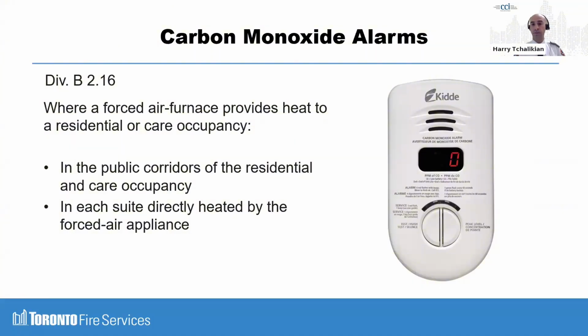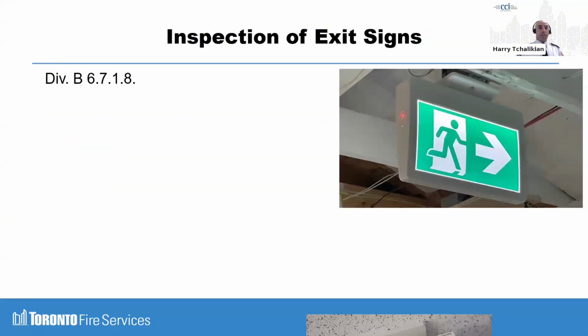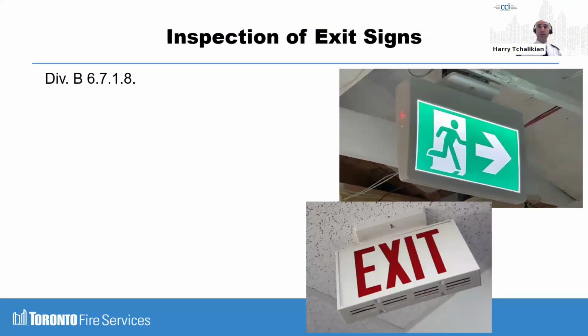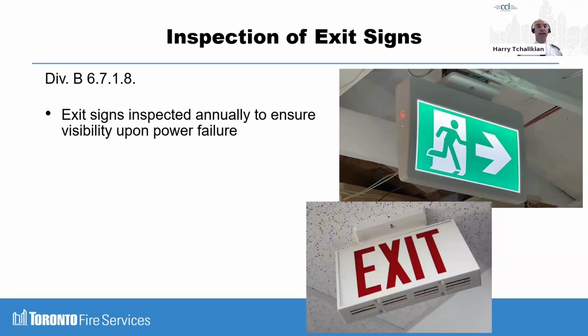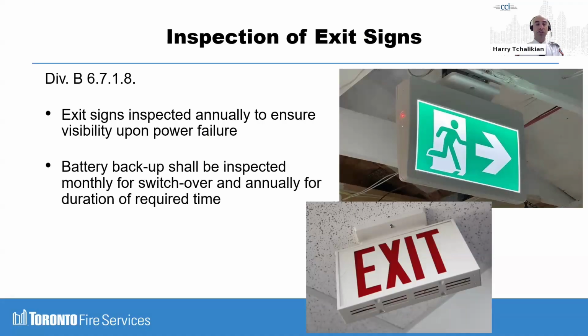Okay, continuing along. Division B 6718, inspection of exit signs. Exit signs inspected annually to ensure visibility upon power failure. This is not new, it's just changed. Battery backup shall be inspected monthly for switchover and annually for the duration of the required time, be it 30 minutes or 2 hours. This is not a new requirement, but is a harmonization requirement.